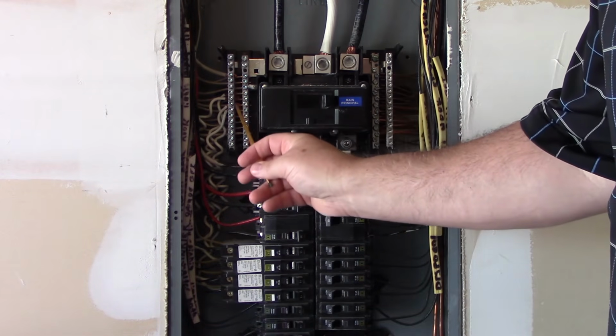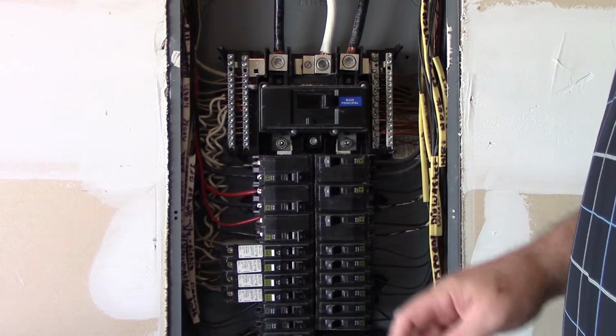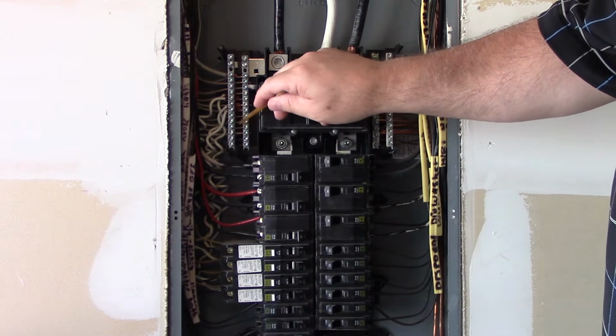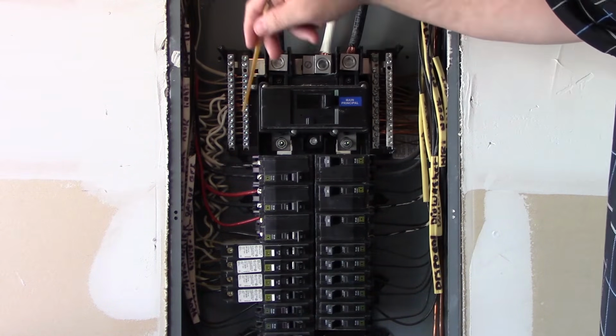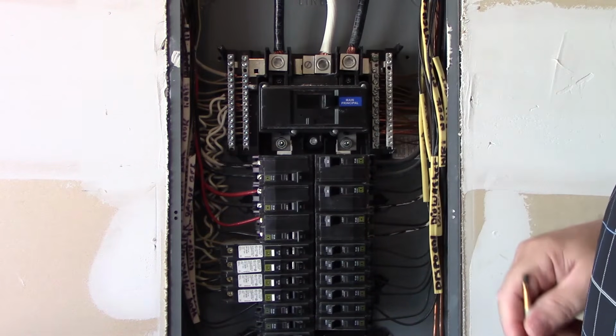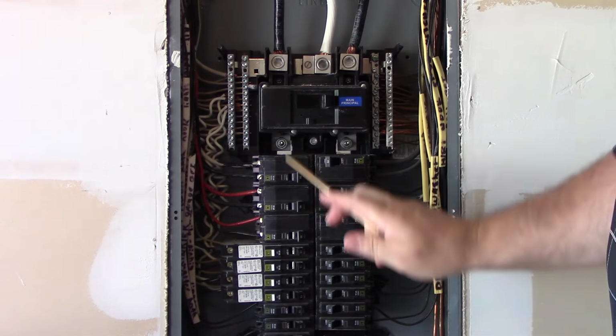And that's why we're looking up here for any discolorations. So that's one of the issues. Again, making sure these are all tight so that you don't get any arc when that load's coming through the circuit could cause a brownout and an arc out, and that could be a problem as well. All right, so that's what we look for down here.